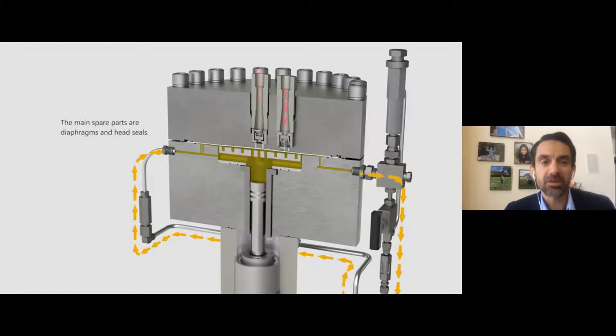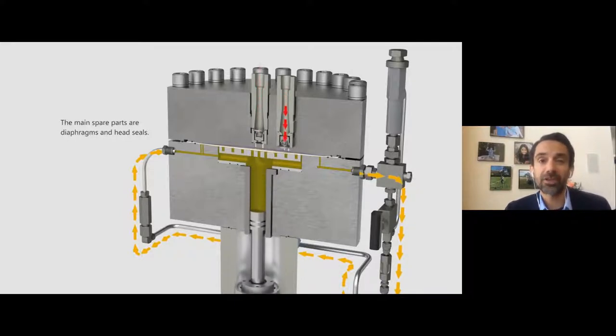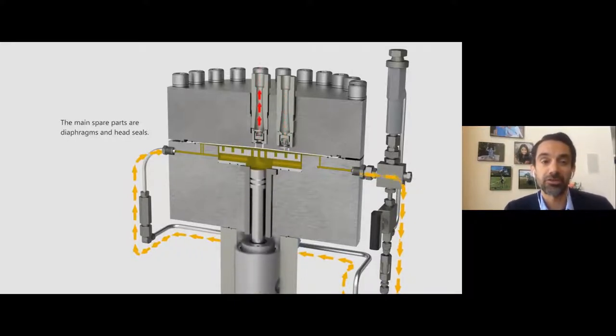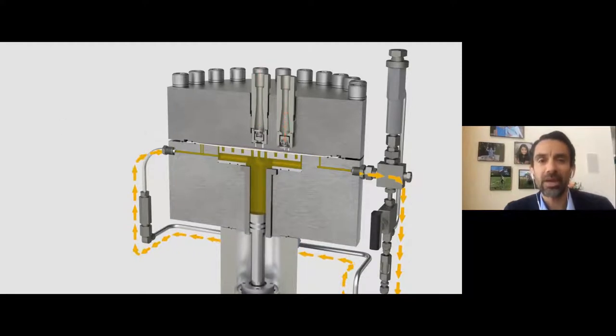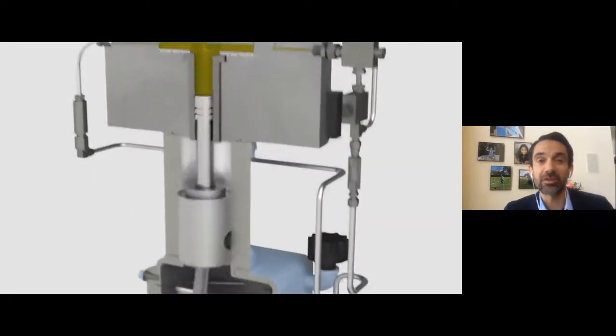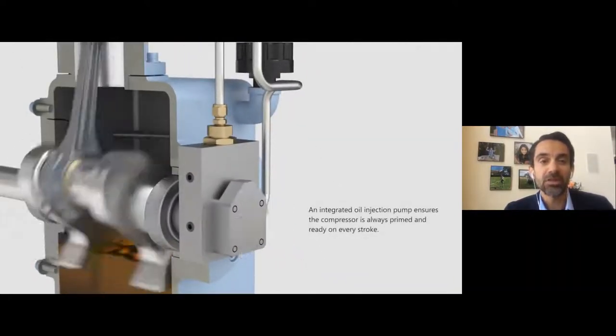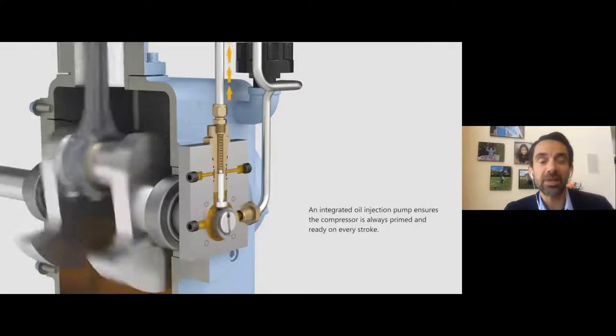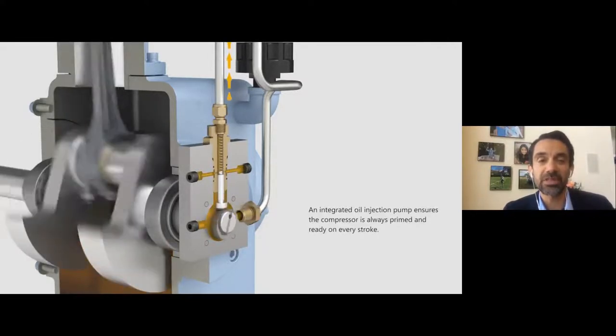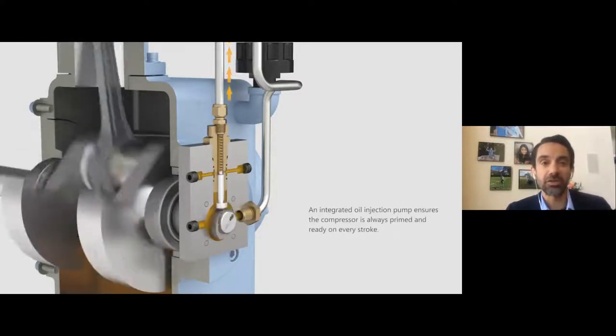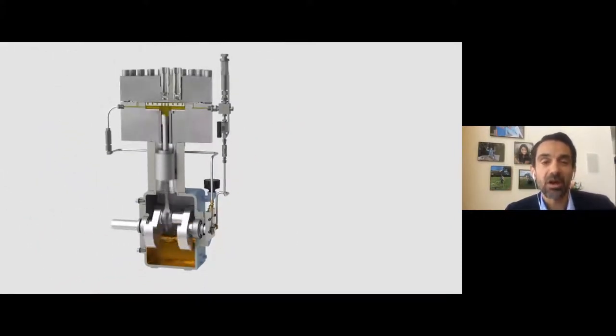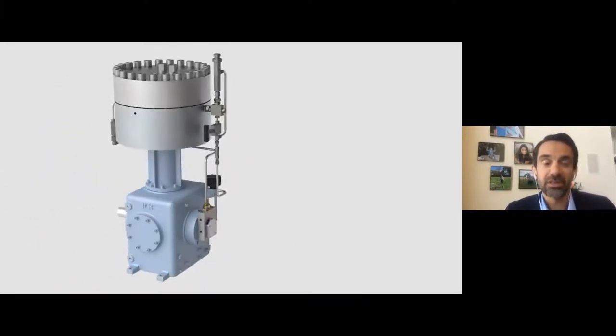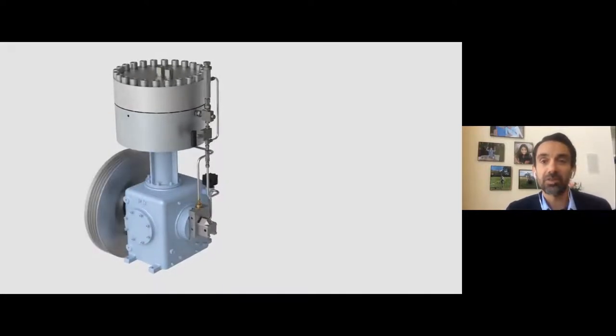This chart shows the gas and oil flow as a function of each other during the compression stroke. We have an oil pressure limiting valve, which regulates the oil pressure that the diaphragms see on the oil side. This is all coupled with a cam mechanism, which ensures priming of the system during each stroke, along with an automatic priming sequence of the compressor during the prime-up and starting sequence.